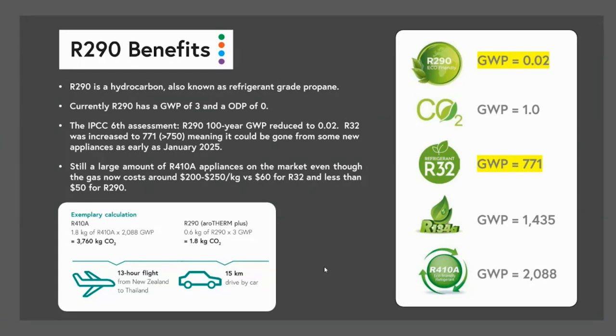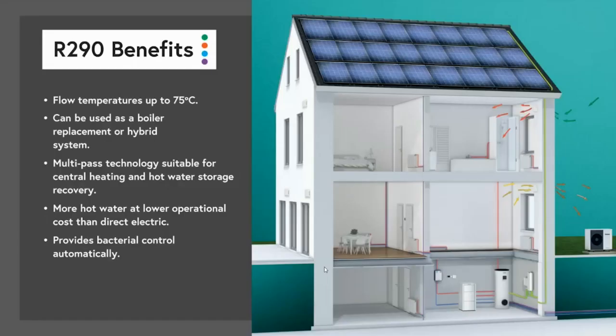And then comparing on the other side, R290, and we're comparing the aroTHERM plus. Now, in order to produce the same amount of heat transfer using propane, we only need 0.6 kilos of refrigerant, and we have a GWP of 3, which gives us 1.8 kilos of CO2. So, a massive reduction in carbon footprint, and that's equivalent to about a 15-kilometer drive in a car. So you can see that the environmental benefits of R290 are quite substantial. So moving on to the next slide.